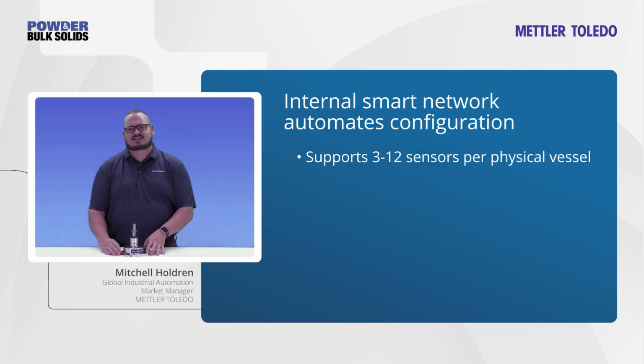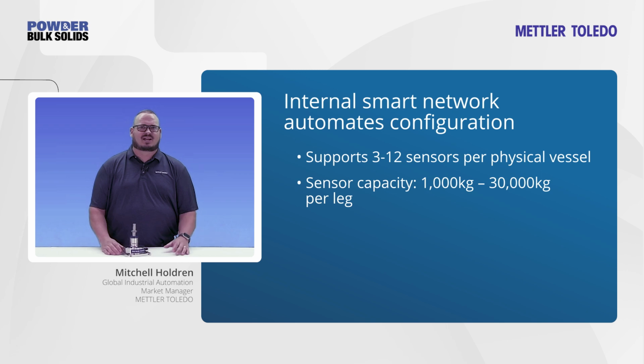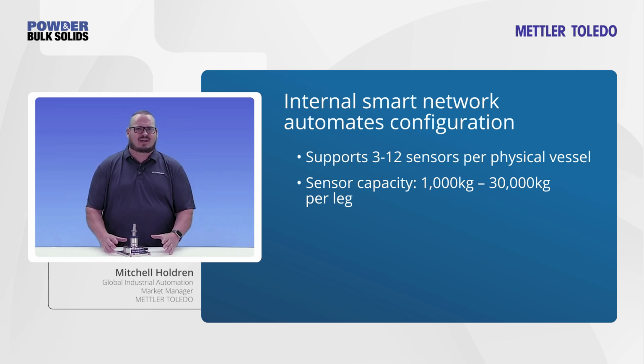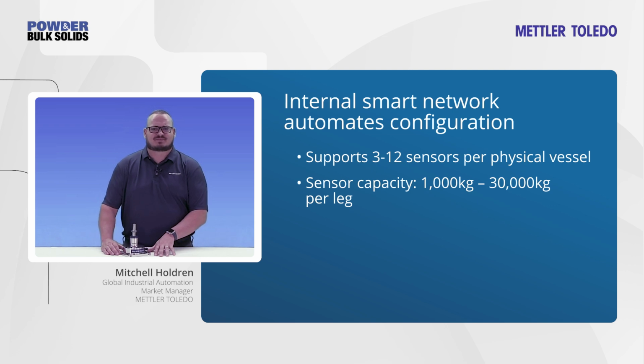You just have to have legs. And then the sensor capacity, you're looking from about 1 ton to 30 tons per leg. So again, even if you have, let's say, 3 legs at 1 ton, you can go below that. You can get all the way up in a case of a 3 leg at 30 tons, you're at about 90 tons, so 90,000 kilograms. So it covers a really, really wide range of process tanks and vessels.